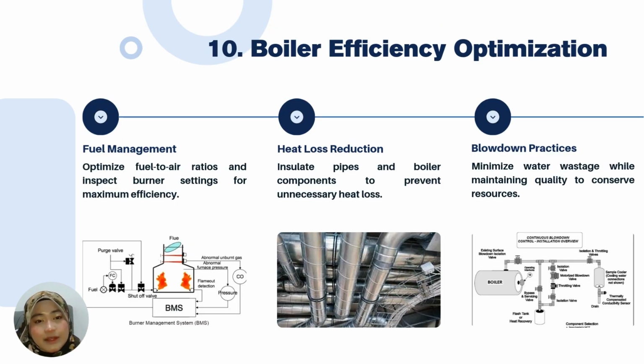Lastly, we have boiler efficiency optimization. To optimize smoke tube boilers, we need to have fuel management, heat loss reduction, and also blowdown practices. Fuel management can be said to optimize fuel to air ratios and inspect burner settings for maximum efficiency, as we can see in the diagram regarding the burner management system. Whereas heat loss reduction revolves around insulating pipes and boiler components to prevent unnecessary heat loss. In this diagram, we can see the pipes are insulated with fiberglass. Whereas the last point would be blowdown practices. Blowdown practices minimize water wastage while maintaining quality to conserve resources. Here we can see a continuous blowdown control installation overview.